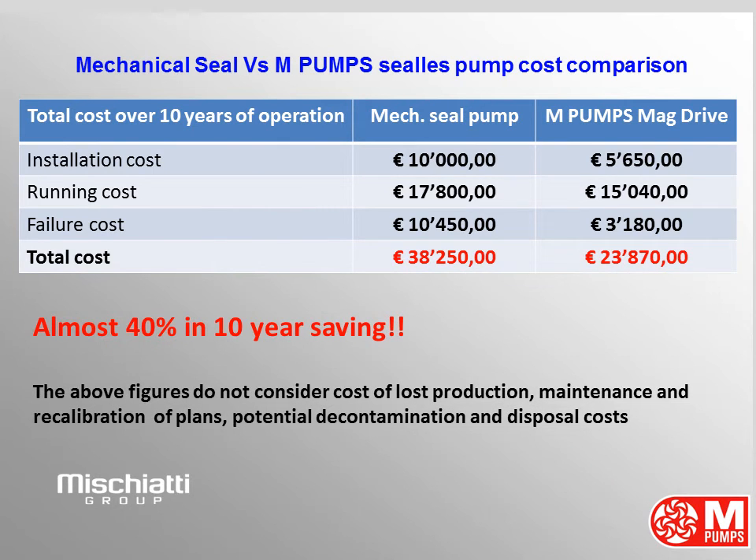Mechanical Seal vs. M-Pumps Magnetic Drive Pump — Total Cost Comparison over 10 years of operation. Installation cost: 10,000 euros vs. 5,650 euros. Running cost: 17,800 euros vs. 15,040 euros. Failure cost: 10,450 euros vs. 3,180 euros. Total cost: 38,250 euros for the mechanical seal pump and 23,870 euros for the M-Pumps magnetic drive pump. In 10 years you save 14,380 euros with M-Pumps on just one pump. If you have 10, 100, or 1,000 pumps installed, imagine how huge the savings can be. With M-Pumps you can save almost 40% of cost.